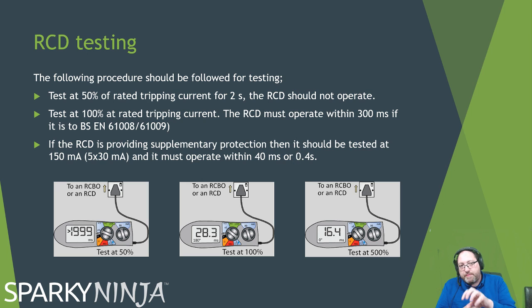Make sure you do it before you do the functional. Okay, and if your tester has the ramp function, might be a good idea afterwards to see if it's nuisance tripping or if it's very close to the lower limit, but it's not really essential. Okay. It's important to do this after the earth fault loop impedance tests though, because obviously you can have a built up voltage on the surrounding earth parts if there's no good earth.